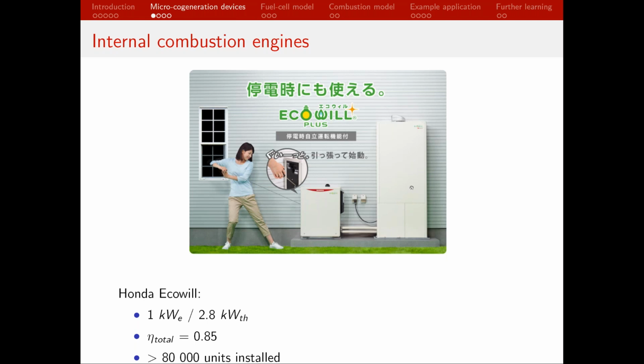This system is sized at about 1 kilowatt electrical output, close to 3 kilowatts of thermal output, and has a combined efficiency of about 85%, meaning that perhaps about 30 to 35% of the fuel's energy release can be converted to electricity, and another 50% or so can be converted to thermal energy.